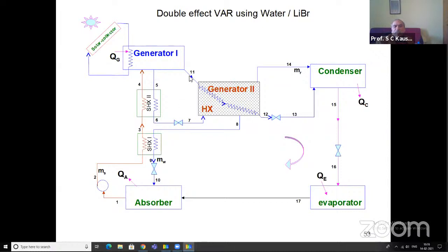So we have two-stage refrigerant vapor generation. First stage refrigerant vapor generation, and then second stage vapor generation. The left behind solution is then passed through this expansion valve, reduced in pressure, and then it goes to the absorber. While this vapor, reduced in pressure, is then condensed here, so it is mixed with the condensate of this second stage refrigerant liquid. After mixing in this condenser, it is passed through this expansion valve and then evaporated.